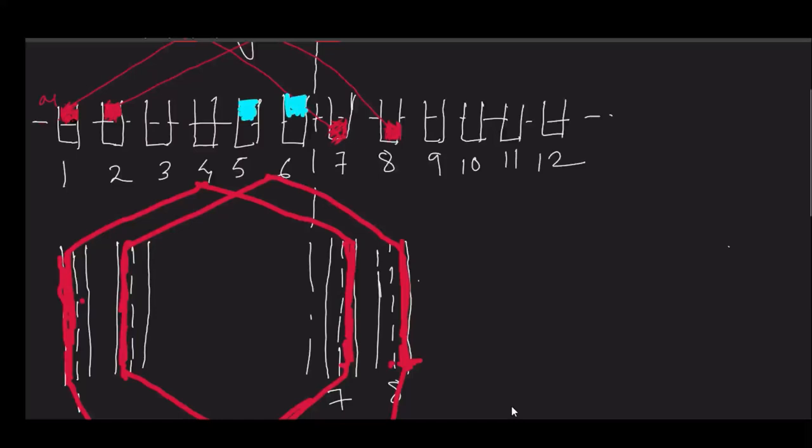Very easy. See, this is 1. So if you take 5, then it is 4. 5 minus 1 is 4, and the adjacent slot angle is 30 degrees, so 4 into 30 is 120 degrees. And similarly from 2 to 6, it is like this. So if you draw them like here, then you can find it is like this. Again this is in the upper layer, so it is the left channel.